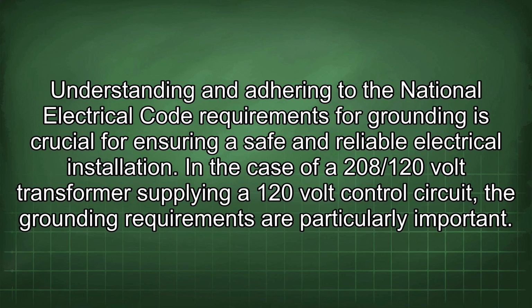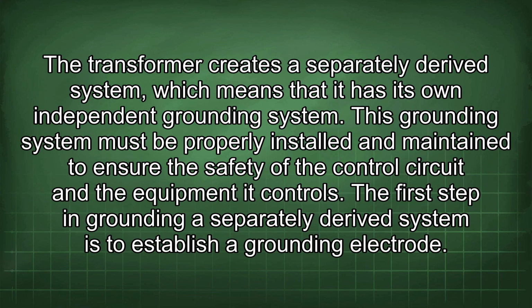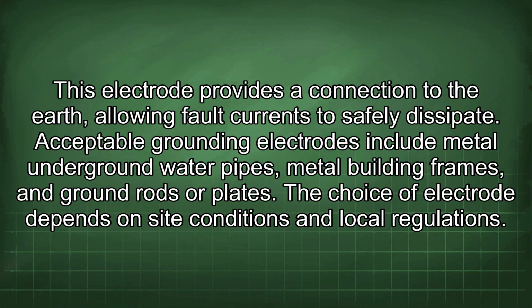In the case of a 208/120-volt transformer supplying a 120-volt control circuit, the grounding requirements are particularly important. The transformer creates a separately derived system, which means that it has its own independent grounding system. This grounding system must be properly installed and maintained to ensure the safety of the control circuit and the equipment it controls. The first step in grounding a separately derived system is to establish a grounding electrode. This electrode provides a connection to the earth, allowing fault currents to safely dissipate. Acceptable grounding electrodes include metal underground water pipes, metal building frames, and ground rods or plates. Choice of electrode depends on site conditions and local regulations.